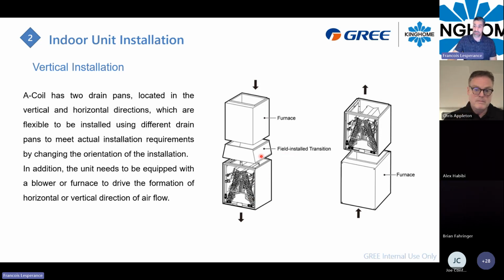You can add a field-installed transition between the A-coil and the furnace. Even if it's a downflow or upflow installation, I recommend you always install a small piece of ductwork between the A-coil and the furnace, because that will help reduce the static pressure, the differential here in your ventilation. By adding a small transition piece of ductwork right here, that will help the airflow go through the A-coil and reduce the static pressure of the system. So sometimes when you have an airflow issue, adding a small part of ductwork here can reduce the pressure in the ductwork.